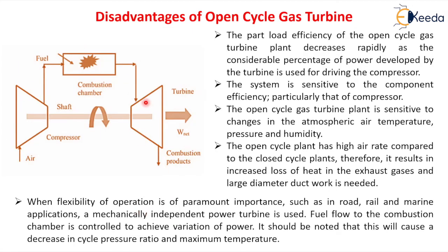Now let's see some disadvantages of open cycle gas turbine power plant. The part load efficiency decreases — part load efficiency is less for open cycle gas turbine. The system is sensitive to component efficiency: if compressor efficiency is less or turbine efficiency is less, the efficiency of the complete plant will be less. Further, the open cycle gas turbine power plant is sensitive to changes in atmospheric air temperature, pressure, and humidity. The open cycle plant has a high air rate compared to the closed cycle plant.